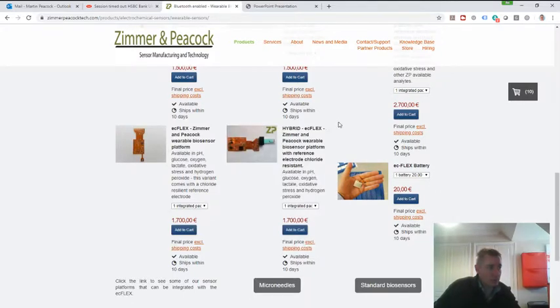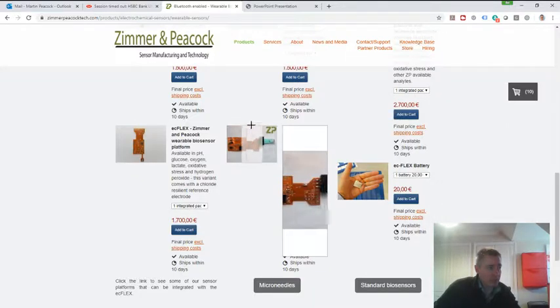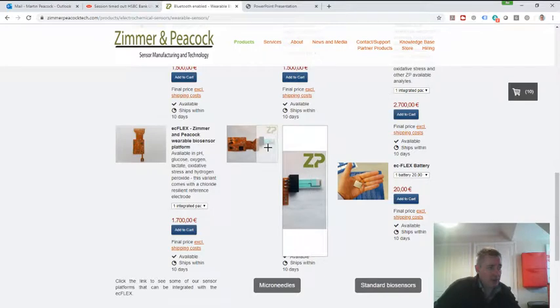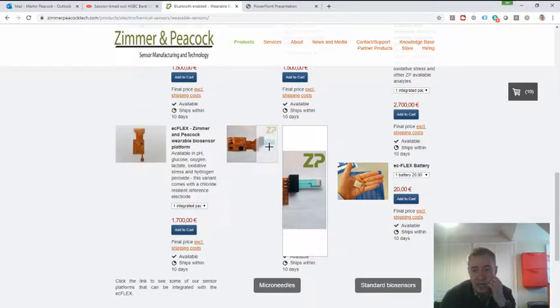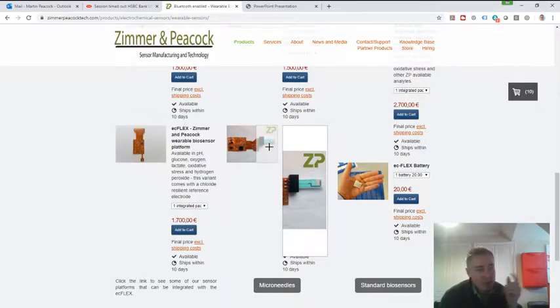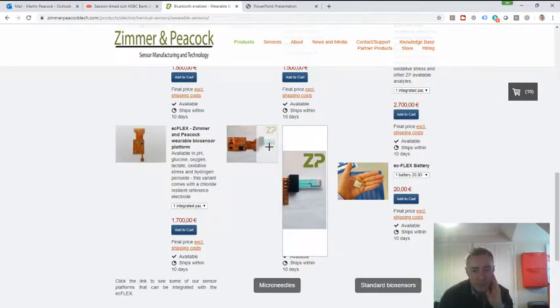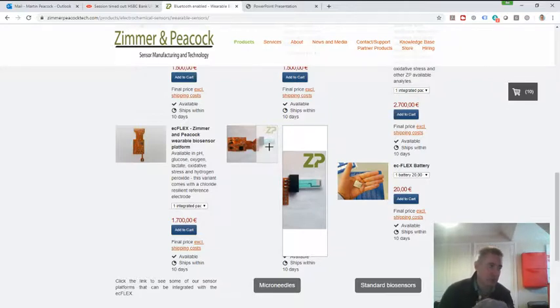So when we talk about the 1700 pounds, that's for the electronics, this little patch here, and then you can buy different types of sensors to click in there. If you want to do lactate and glucose, let's say at the same time, this will only do one at a time. You cannot run them both in parallel.